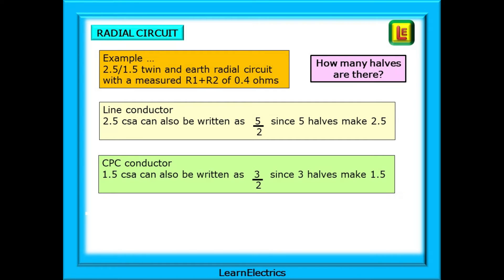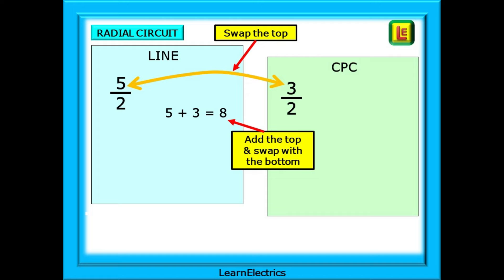Let's calculate r1 and r2 for the given radial circuit. We are using 2.5 by 1.5 twin and earth installed in a radial circuit with a measured r1 plus r2 of 0.4 ohms. To start, we must determine how many halves there are in each conductor. The line conductor is 2.5 CSA, which can also be written as 5 halves — 5 over 2. The CPC is 1.5mm CSA, which can be written as 3 halves, or 3 over 2. We will first swap the top numbers, then add the top numbers together and swap these for the bottom numbers — all will make sense on the next slide.